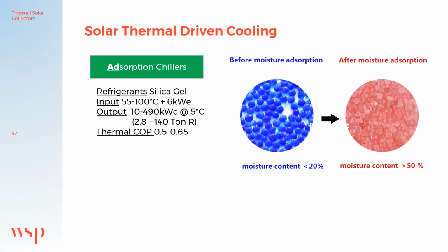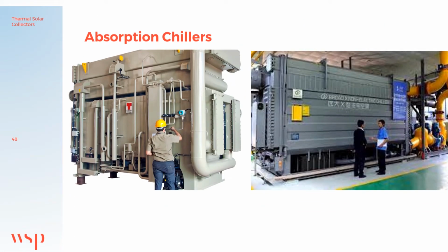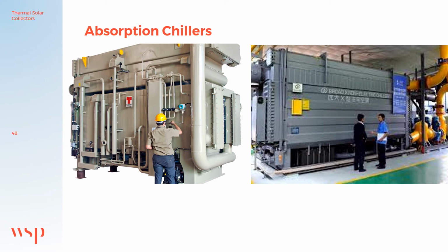Adsorption chillers use silica gel as refrigerant and generate chilled water at 5 degrees C or 41 degrees Fahrenheit and is commercially available in capacities between 2.8 to 140 ton. These are examples of absorption chillers.